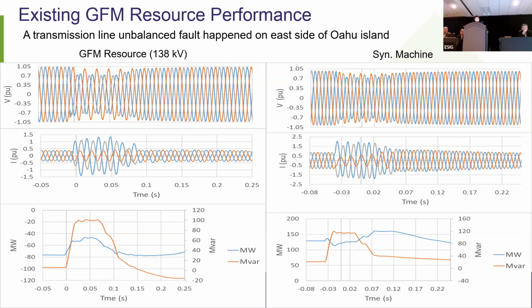Sorry that the time axes are not that aligned among these three curves, but I think the performance is very clear. And for the sake of comparison, on the right side I put the synchronous machine response. We also have DFR on some synchronous machines, but the DFR monitors the machine terminal side, so it's not the 138 kV side. So the voltage curves look a little bit different. Maybe we can focus on the instantaneous current curve. I would say for these two resources, the instantaneous current responses are very similar.